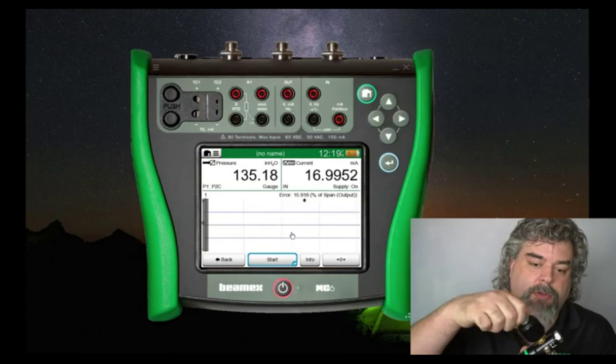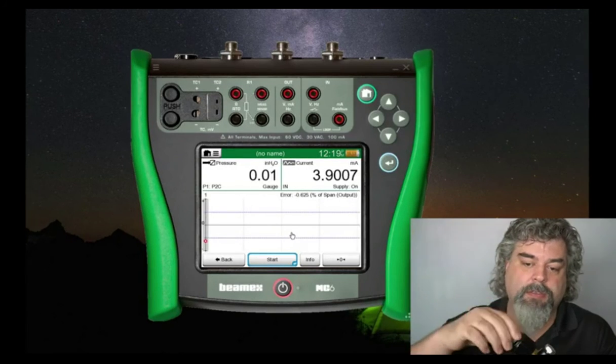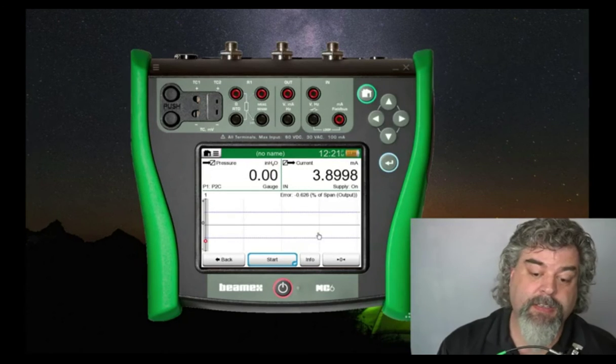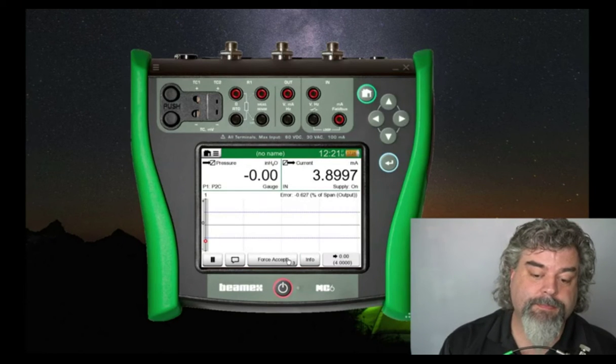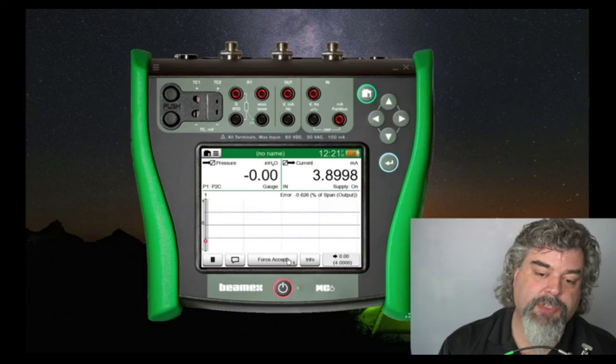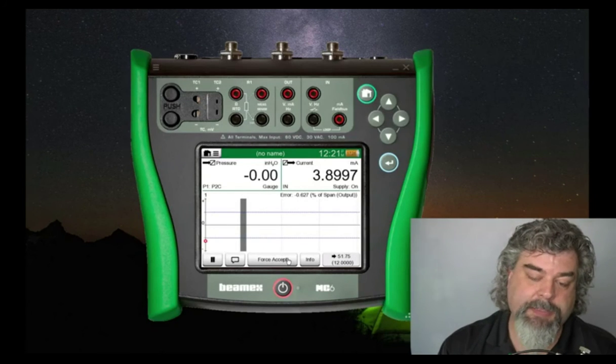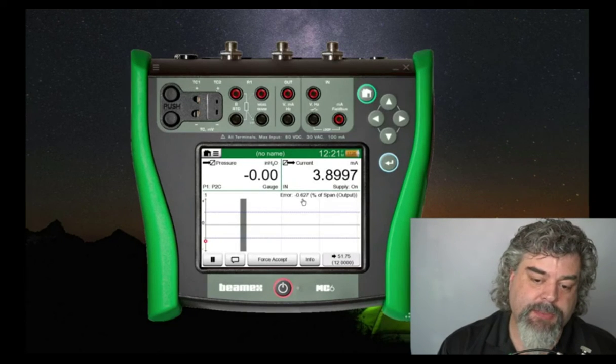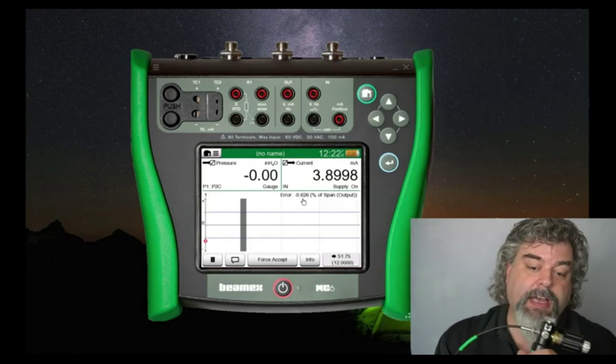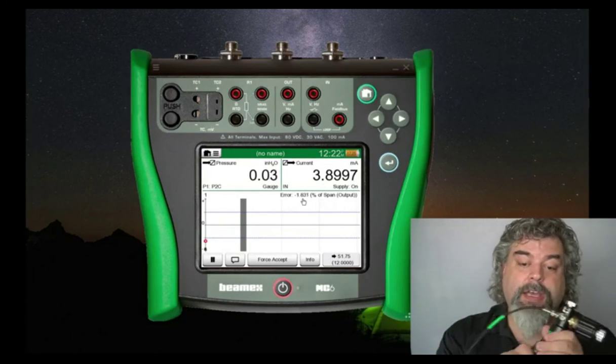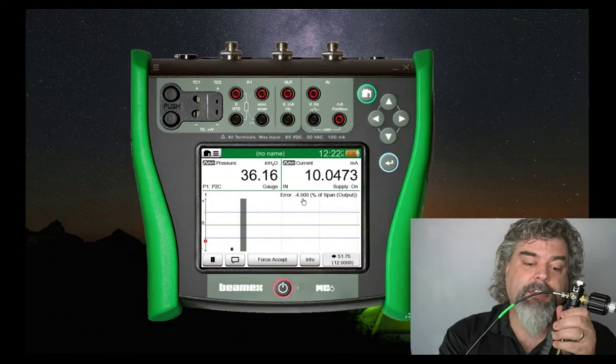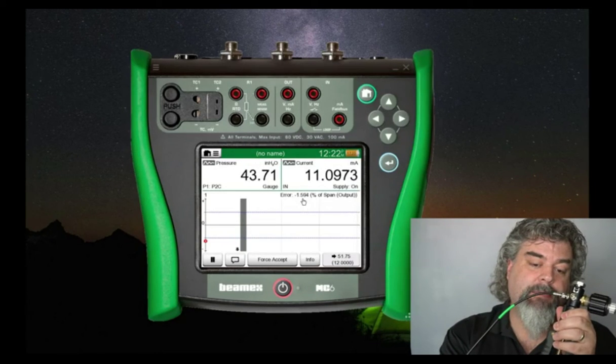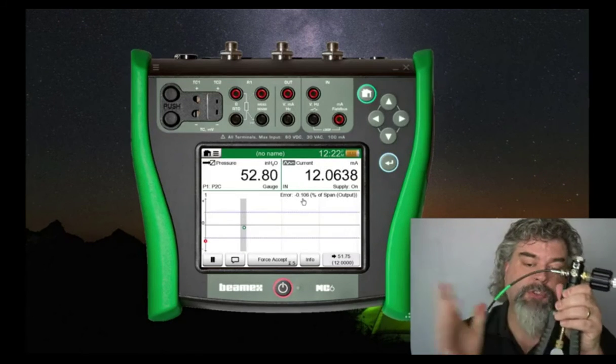So let me just open the vent, and I don't need to re-zero it. Let me just start it. Counting down, we have 0 in, and we want 4 milliamps out. So right here it says negative 0.627% of span error. Now we'll close off the vent, and I will pressurize this to get us into the 50% area. And I'm just doing a slow squeeze on that.